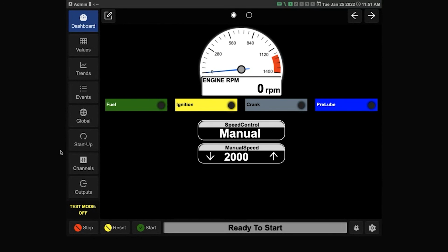So if you have a system that needs updated to 2.1, you're going to need 2 things. You're going to need a micro SD card to insert into the SOM module and update all the software to 2.1, but you're also going to need the ST-Link programming tool so that you can update the firmware on the controller module and the terminal module.